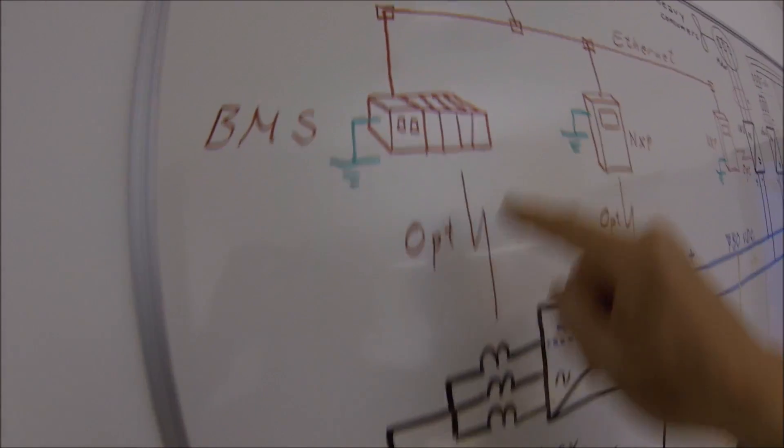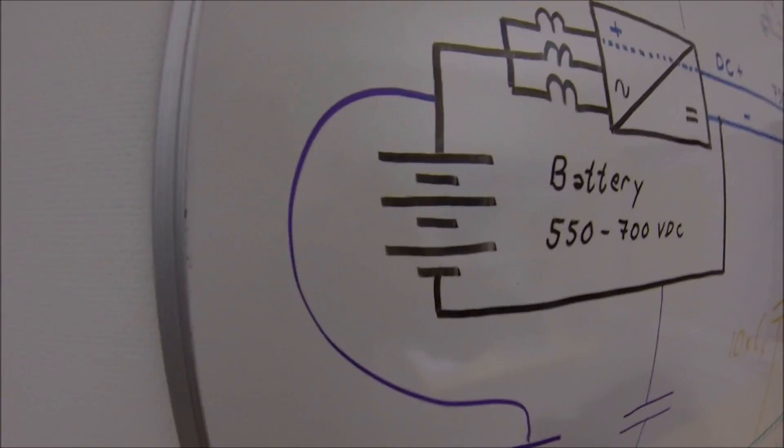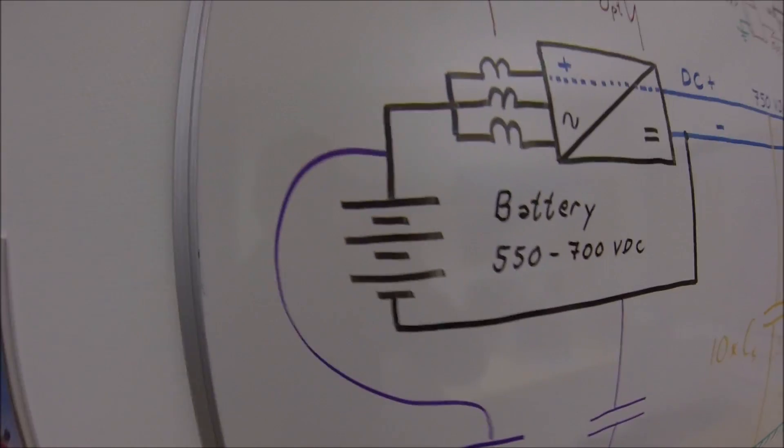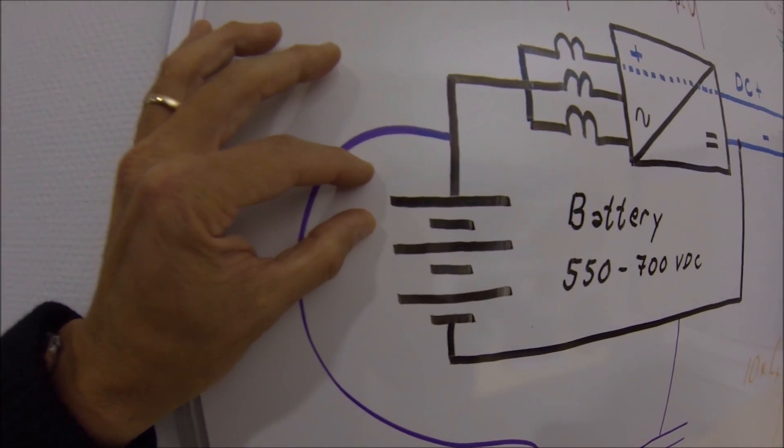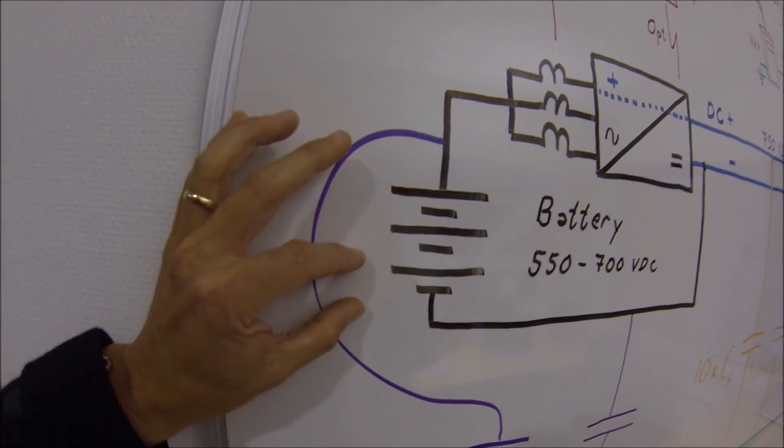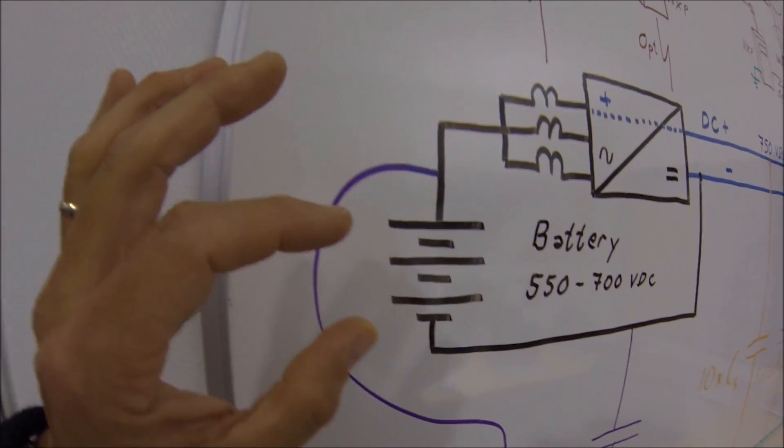Also, you could have the situation where the battery management system has problems communicating with its cells. What has happened? Well, voltage measuring devices and also cell balancing devices here should be galvanically isolated from the BMS.